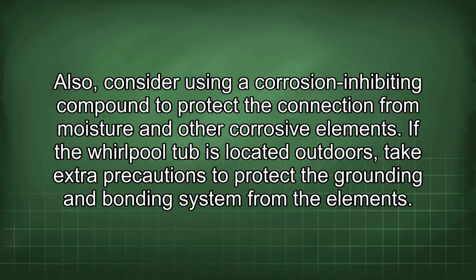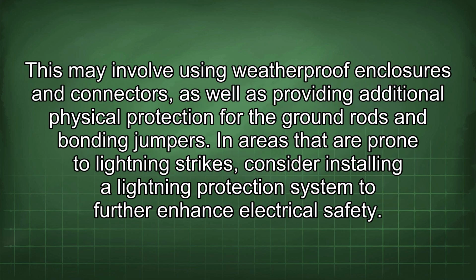Also, consider using a corrosion-inhibiting compound to protect the connection from moisture and other corrosive elements. If the whirlpool tub is located outdoors, take extra precautions to protect the grounding and bonding system from the elements. This may involve using weatherproof enclosures and connectors, as well as providing additional physical protection for the ground rods and bonding jumpers.